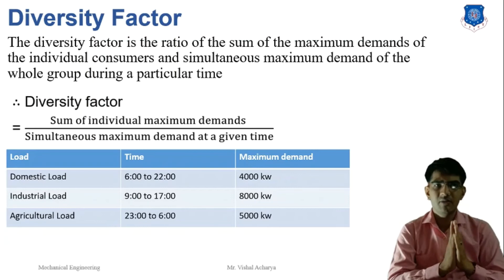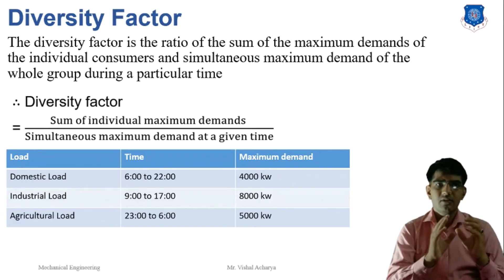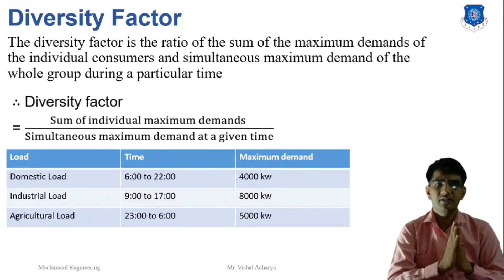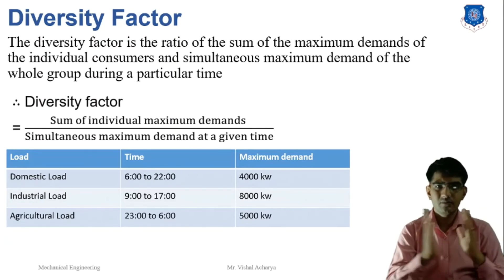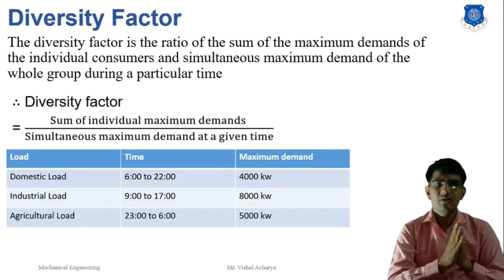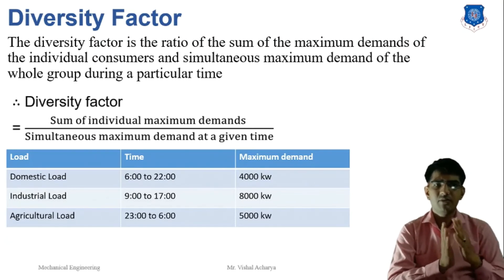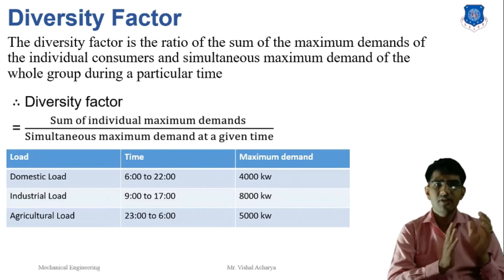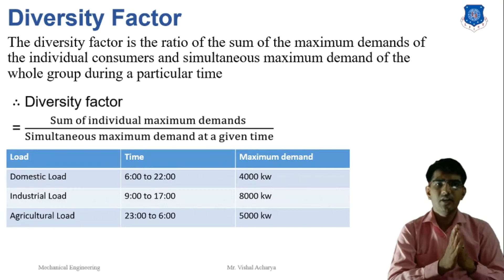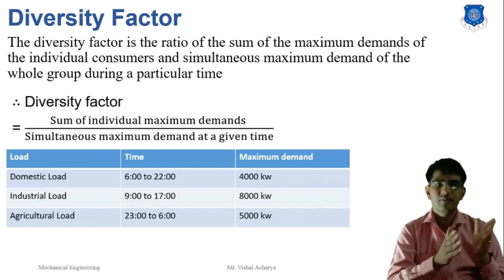In an example with three types of load — domestic, industrial, and agricultural — the sum of the individual maximum demands is: domestic 4000 kW + industrial 8000 kW + agricultural 5000 kW = 17,000 kW. But for the time period 6 to 17, only domestic and industrial loads operate, giving a simultaneous demand of 12,000 kW. So the diversity factor for 6 to 17 is 17,000 / 12,000, which is greater than 1. This same calculation can be done for different time periods.